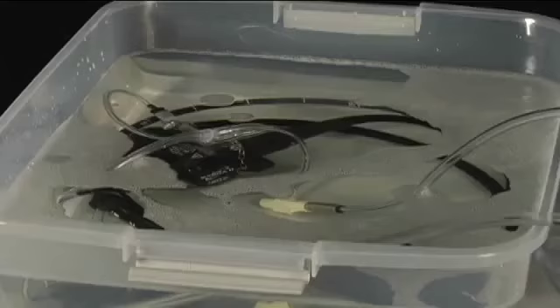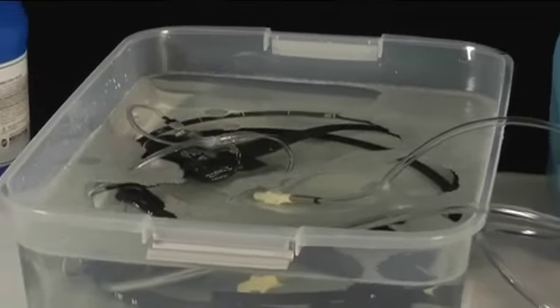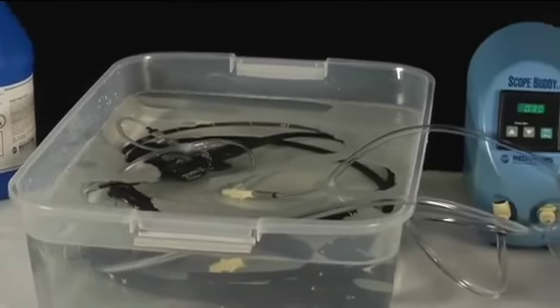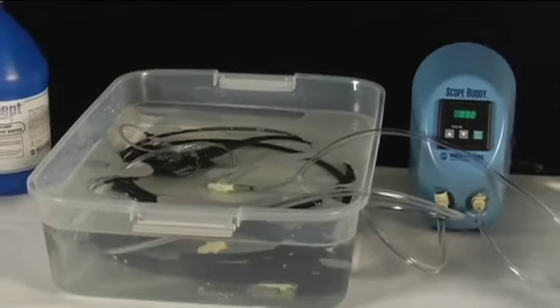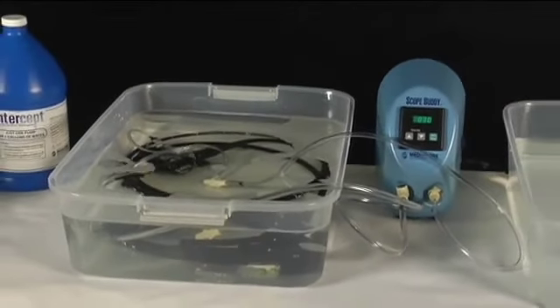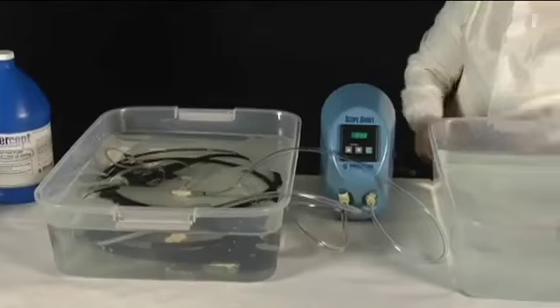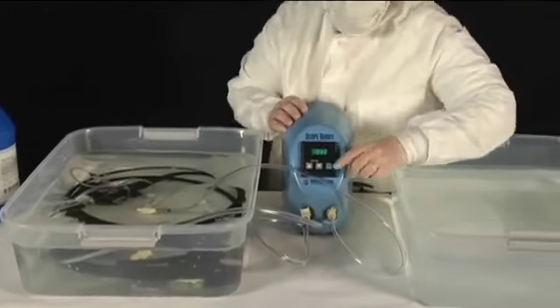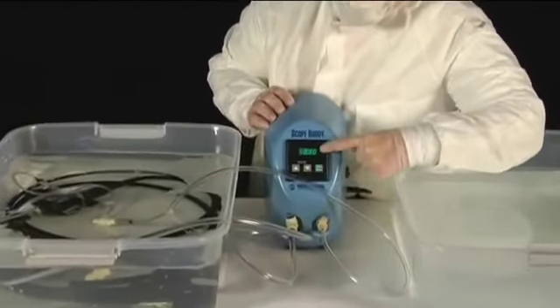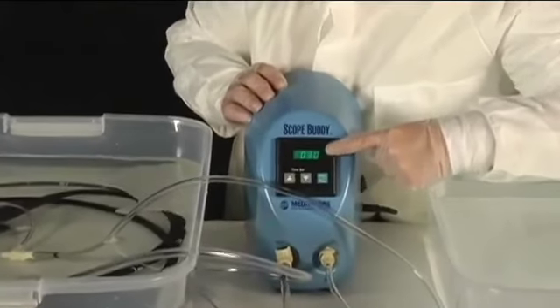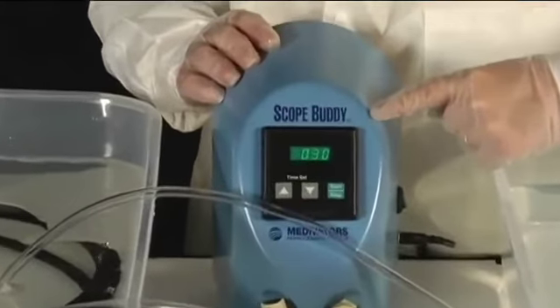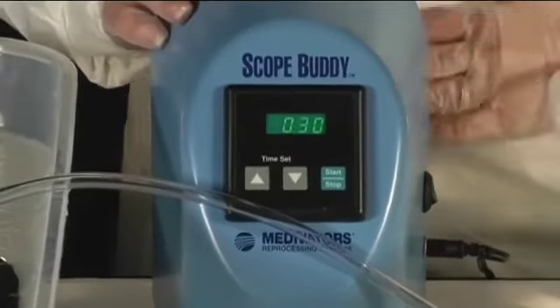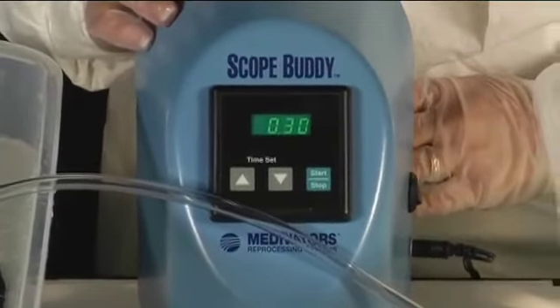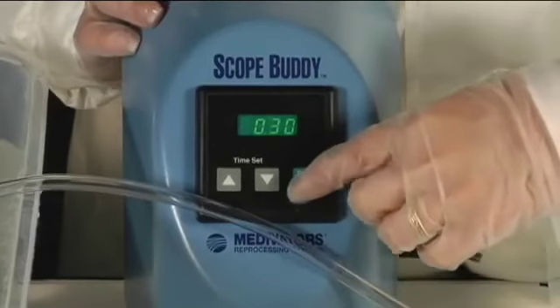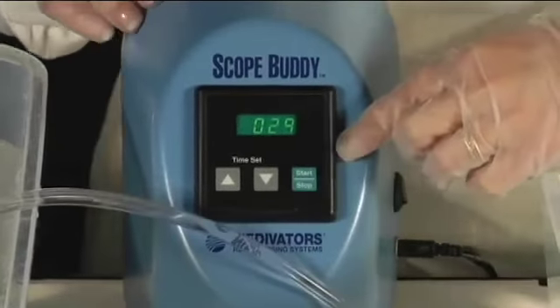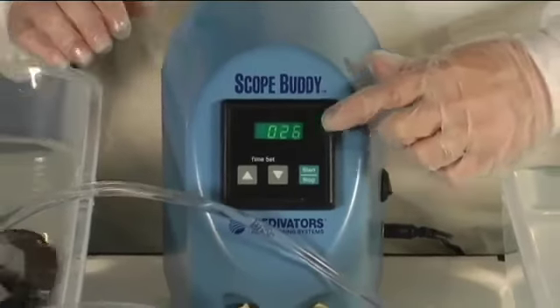The endoscope should now be hooked up to Scope Buddy with the appropriate tubing with the fluid intake line in the detergent. Use the following steps to begin operation of Scope Buddy. Flushing an endoscope with detergent. Using the Scope Buddy front panel arrow keys, set the time until it displays the desired flushing time. Programming times for types of endoscopes are located in the Scope Buddy user manual or on the appropriate Scope Buddy rinse matrix. Press the Start-Stop button to begin the cycle. The timer display will now begin counting down.